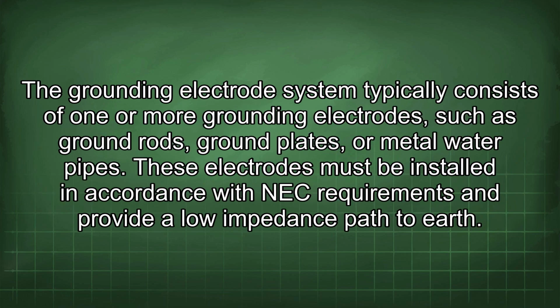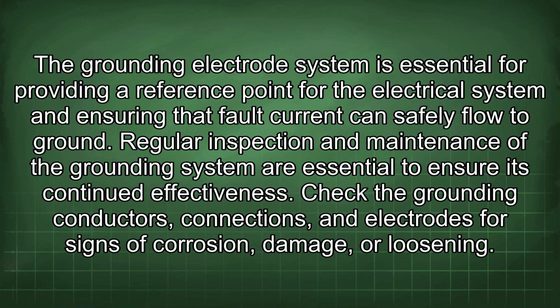The grounding electrode system typically consists of one or more grounding electrodes, such as ground rods, ground plates, or metal water pipes. These electrodes must be installed in accordance with NEC requirements and provide a low impedance path to earth. The grounding electrode system is essential for providing a reference point for the electrical system and ensuring that fault current can safely flow to ground. Regular inspection and maintenance of the grounding system are essential to ensure its continued effectiveness.